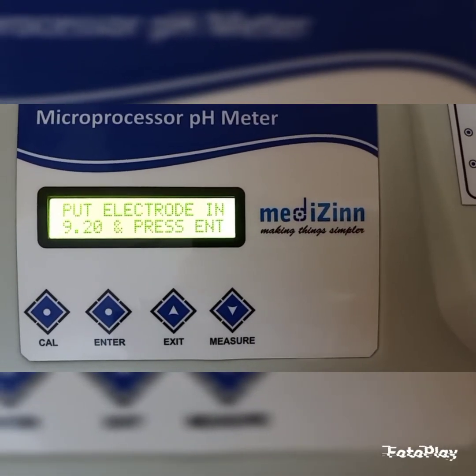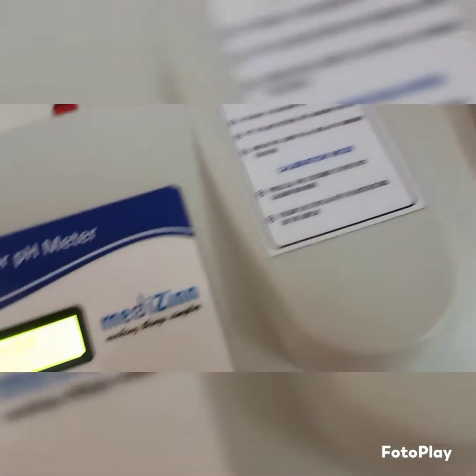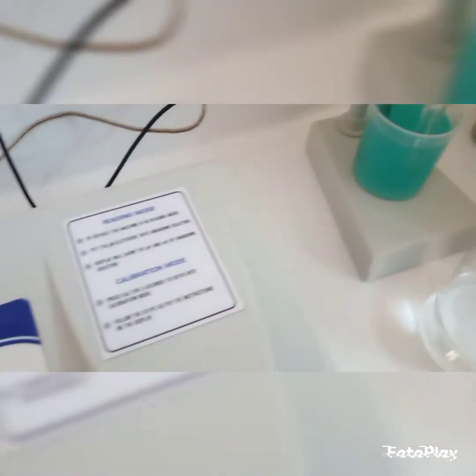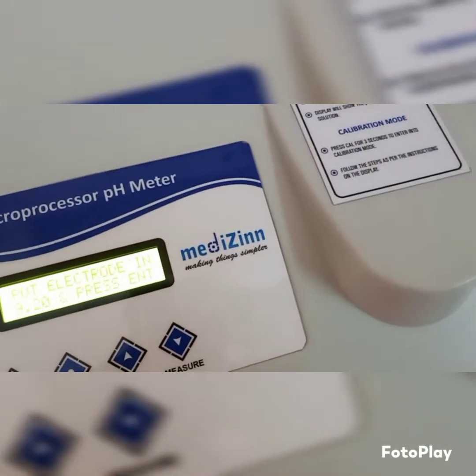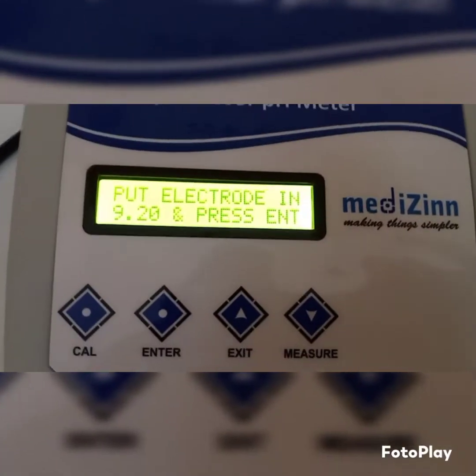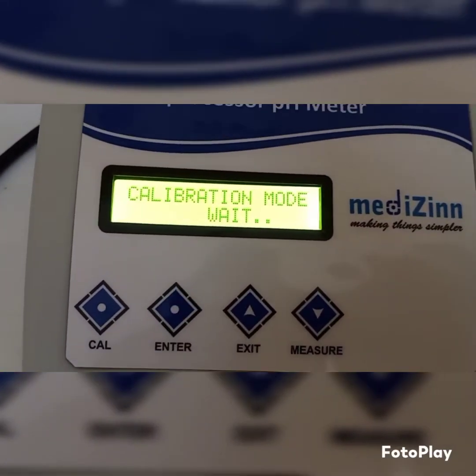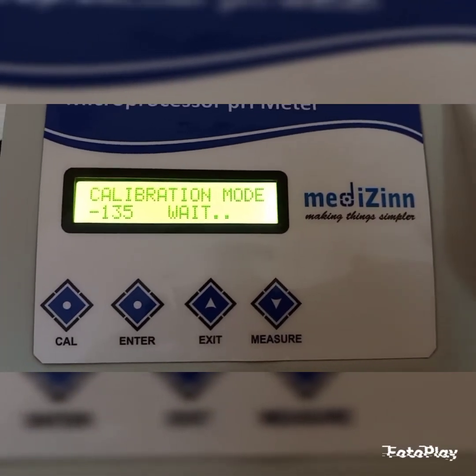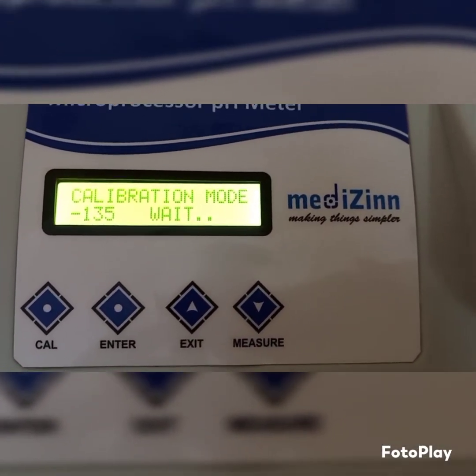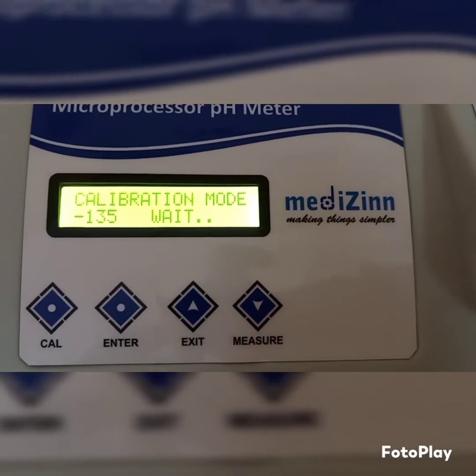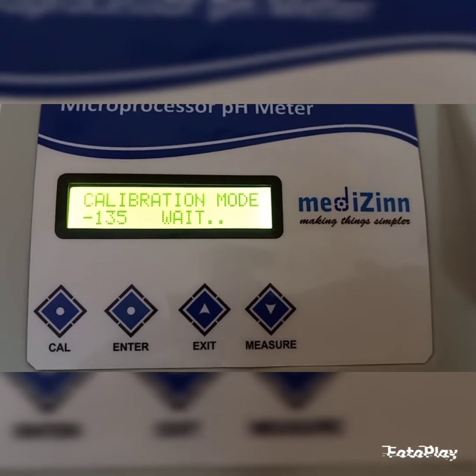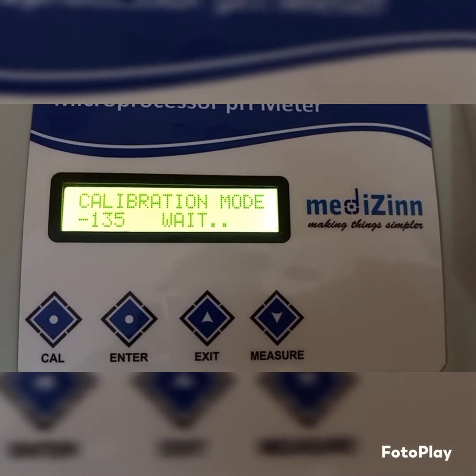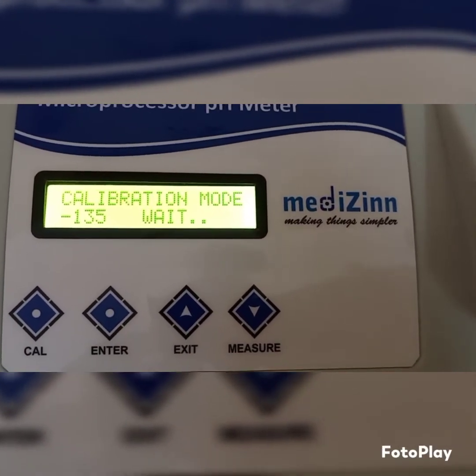Seven pH done. Now again wash the electrode and temperature probe thoroughly using distilled water and put both the things into 9.2 pH buffer. Now put electrode and temperature probe in 9.2 pH buffer, and after that press enter key. Again analog values is in the minus. It's showing that buffer is above 7 pH. Again we have to wait for approximate 2 minutes.